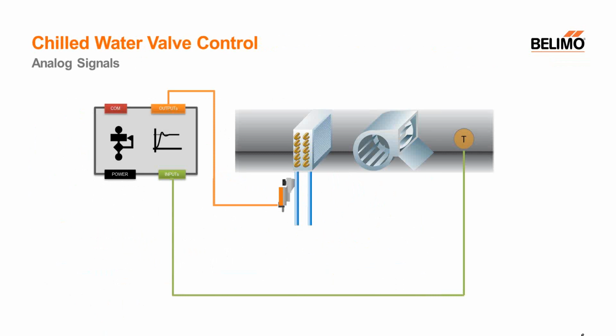So with that out of the way, let's look at a really basic HVAC application. On the left, you have a little DDC controller. It has an output to control a valve actuator on a cooling coil, and we also have an input on that same controller to monitor the temperature on the leaving side of that fan unit. The controller looks at the temperature and compares it to a set point, likely like 55 degrees for cooling. If it needs more cooling, it opens the valve a little bit more. If it needs less cooling, it closes the valve a little bit more. So that's a very simple process.